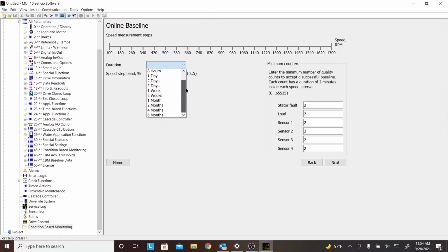So let's say we've got a machine. Let's say it's a conveyor, and we've got a whole bunch of boxes on it or something, and we just can't run that from basically 0 to 1700 RPM in a minute or 2 or 30 minutes. Not to get a true indication of the load. We need to let it run while the application's running. This is what this is for. So while the application is running, this software sits in the background, and it allows you to pick how much time period you want to take before you gather all that baseline data. So from there, you would hit next and move on.